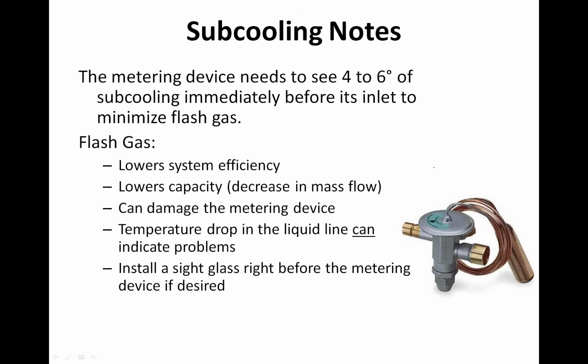If you've ever had air in a spigot when you've gone to draw some water out of a sink, and you know how that air splashes and spitters and sputters out of the faucet, it's exactly what happens inside the TXV. You don't get that nice smooth laminar flow, and it's very, very hard on that metering device. It causes liquid hammer, and it can actually ruin the metering device over time.